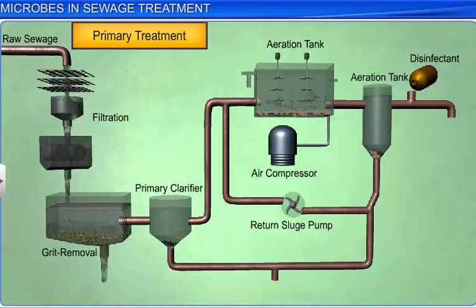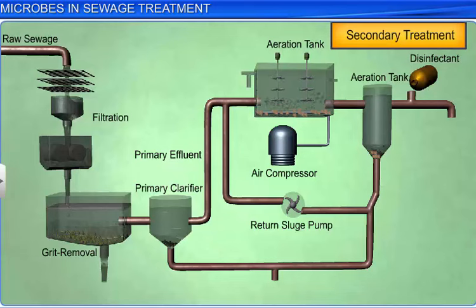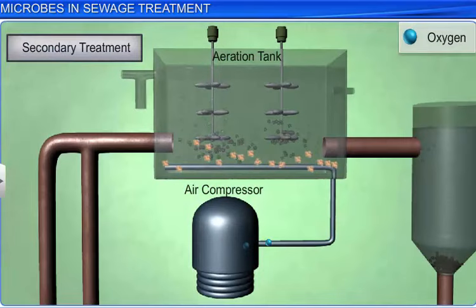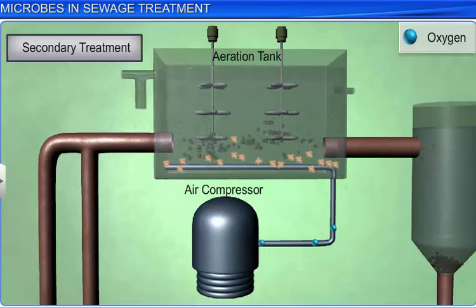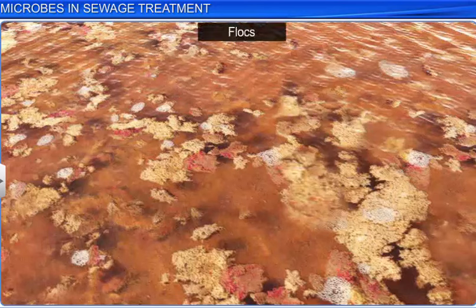Primary effluents are now transferred from the primary settling tank to large aeration tanks for secondary treatment, also known as biological treatment. Secondary treatment aims to reduce organic matter in the effluents. In the aeration tanks, the effluents are constantly agitated mechanically and oxygen is pumped into them. As a result, aerobic bacteria naturally present in the effluents grow into flocs, which are mesh-like structures formed by groups of bacteria in association with fungal hyphae or filaments.